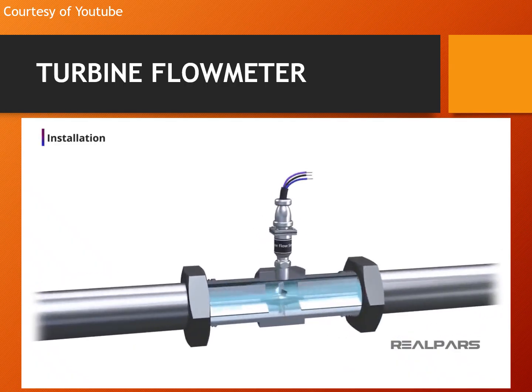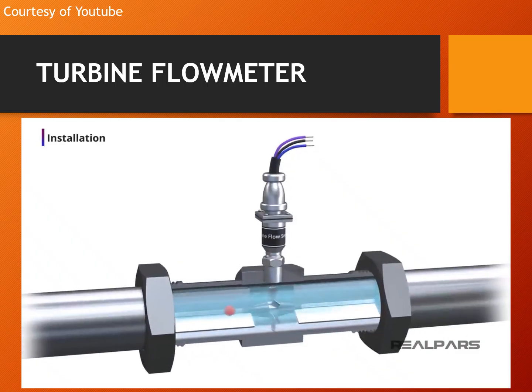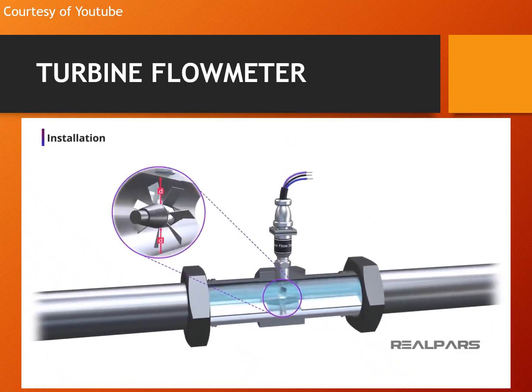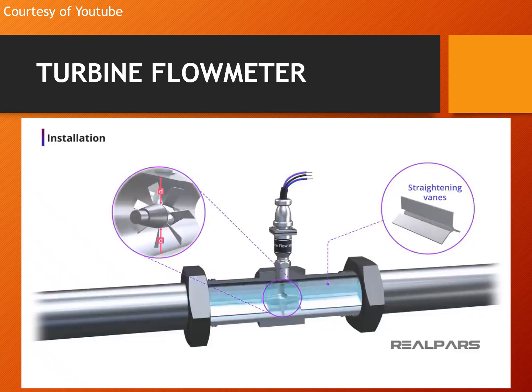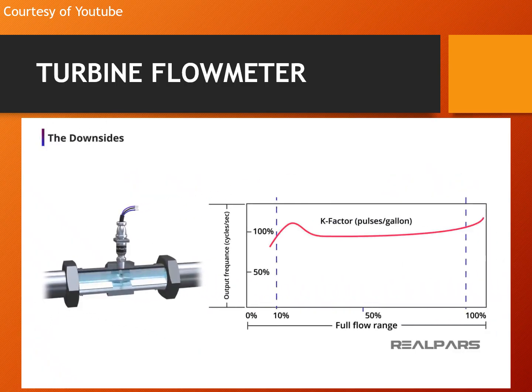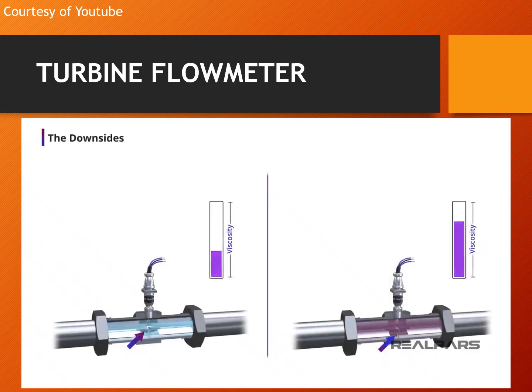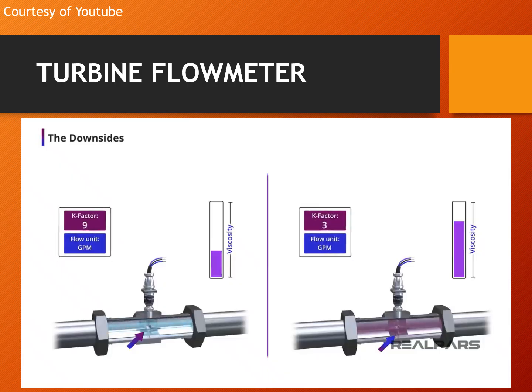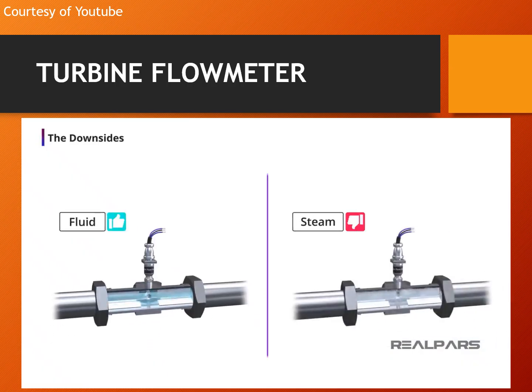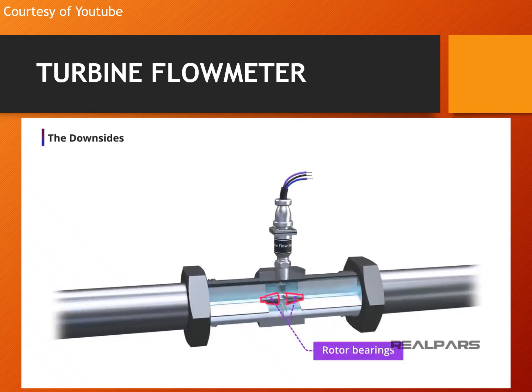The turbine meter can only be used in clean, lubricating fluid, because suspended particles can easily damage the device. The turbine rotor must be positioned in the exact center of the flow, and laminar flow is critical, often requiring straightening vanes. Even though they are one of the most accurate volumetric flow meters in use today, they do have some downsides. The K factor is not always consistent across the entire flow rate measurement range. Turbine flow meters are not accurate at very low flow rates. Viscosity is an issue, as thicker or thinner fluids can change the rotor speed and affect the meter's calibration. Keep in mind that the turbine flow meter K factor was determined at the factory using a specific set of parameters. They are not recommended for steam. As with other mechanical devices, the rotor bearings wear out.